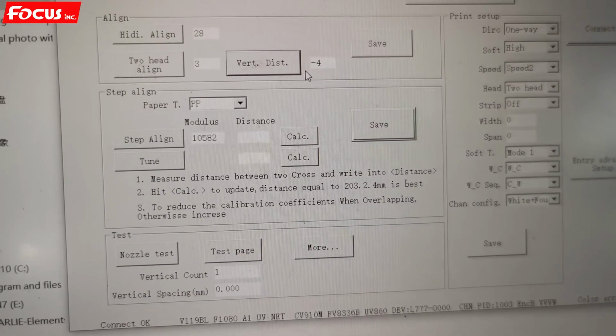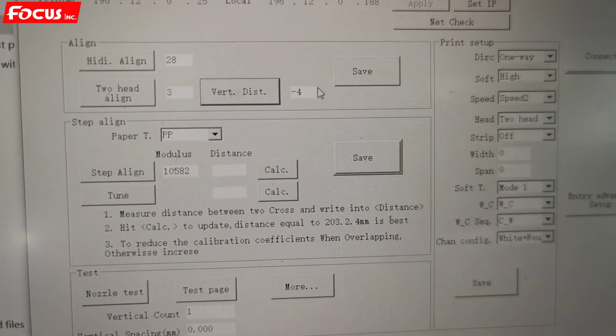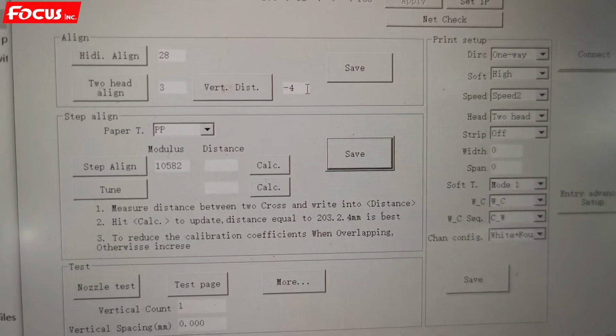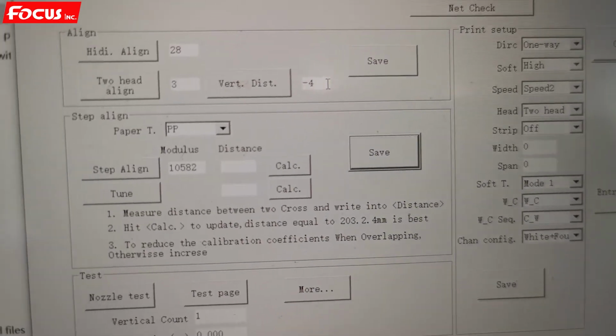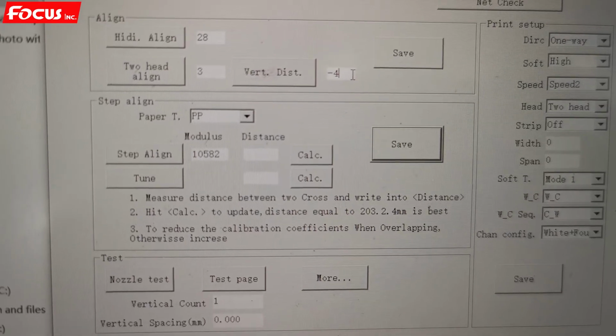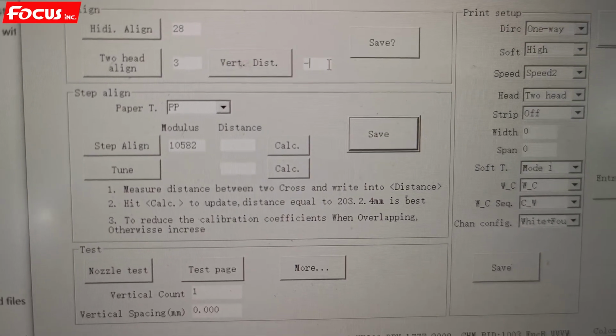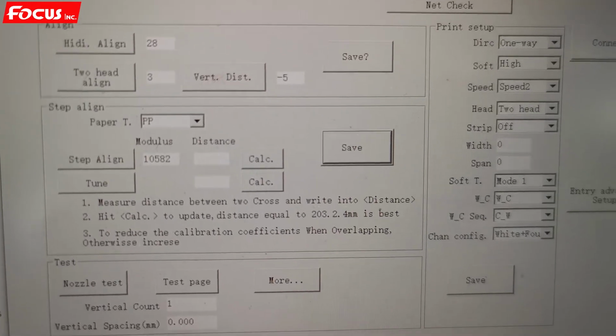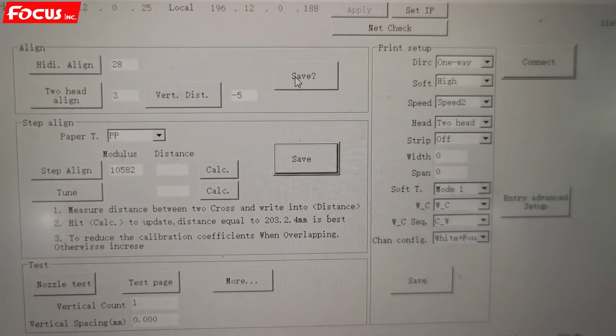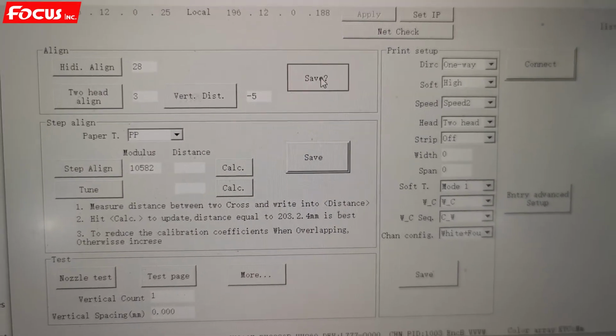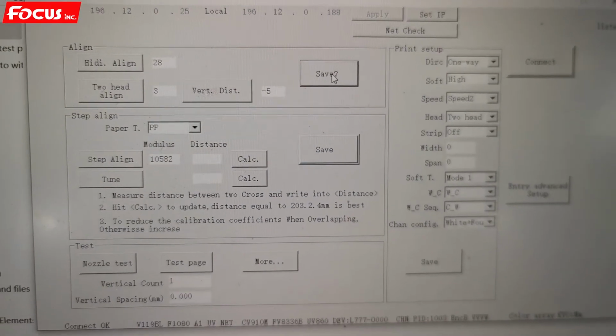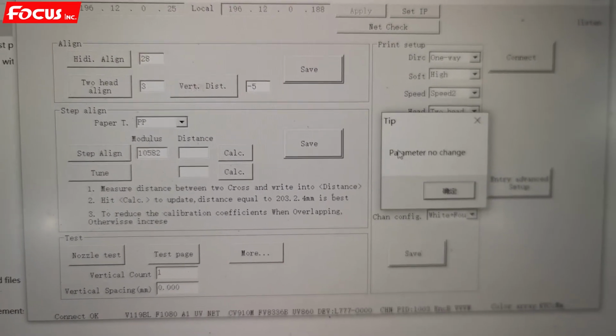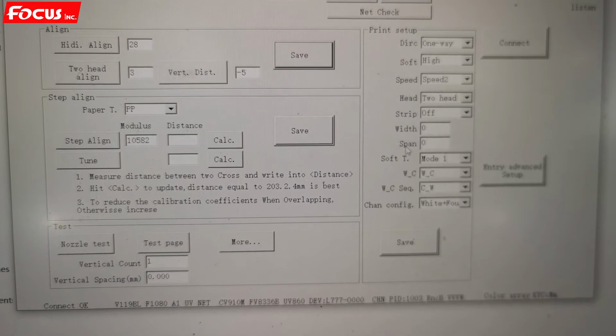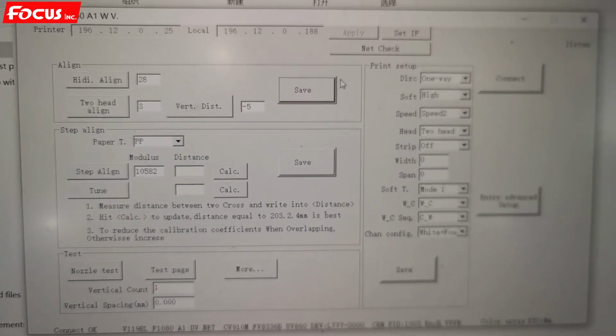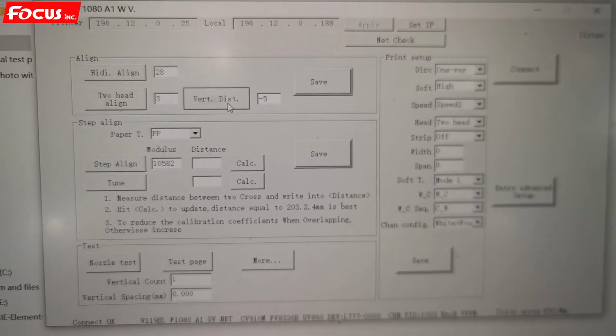Then we go back to the software and we find the number right now is -4. So -4 plus -1 equals -5. Then we put -5 into the software. Then we must remember to press save for the parameter. We press again, then it shows parameter no change. That means it is already written to the board. Then we press the vertical distance again under speed 2.